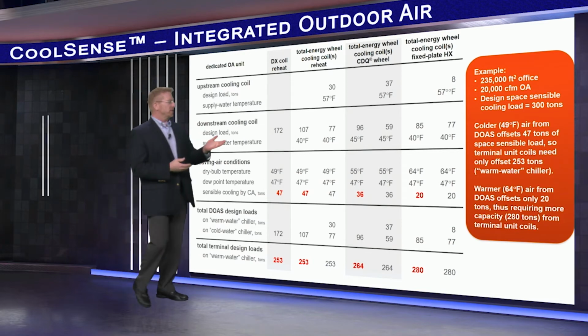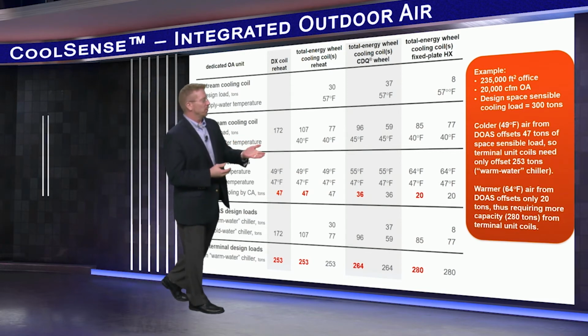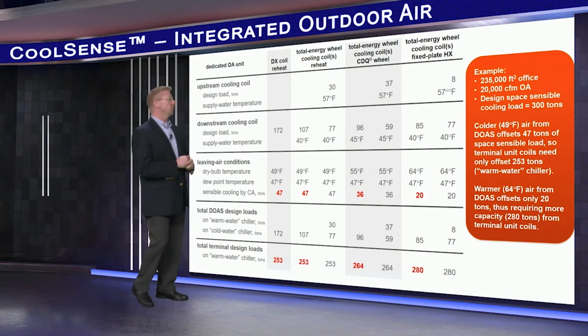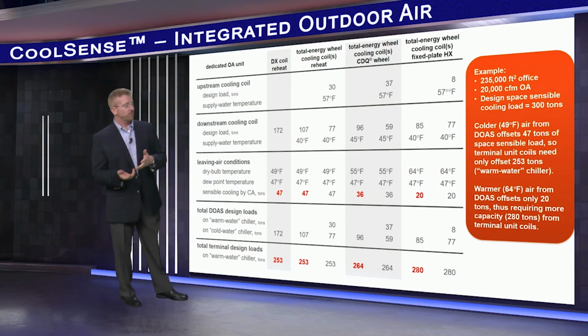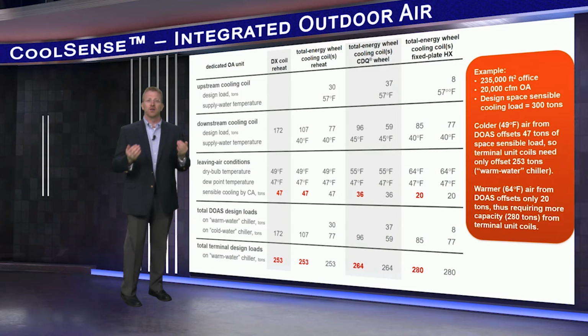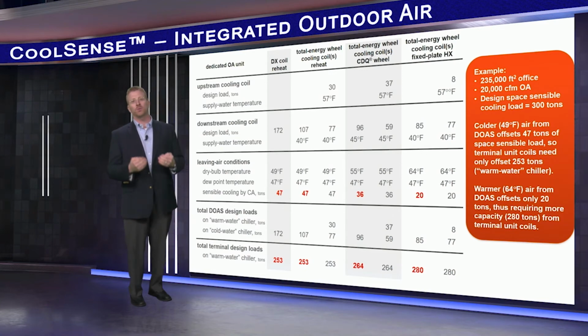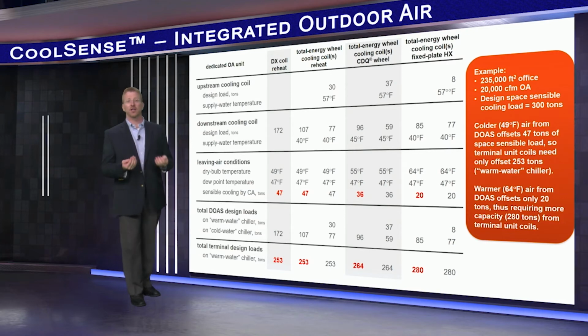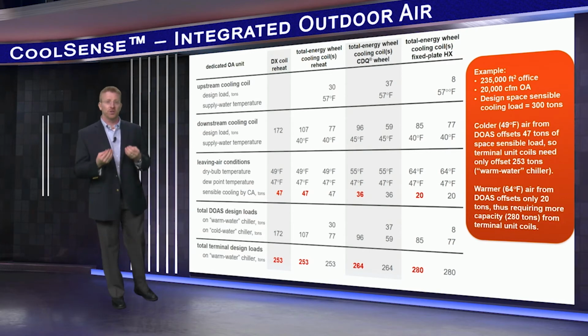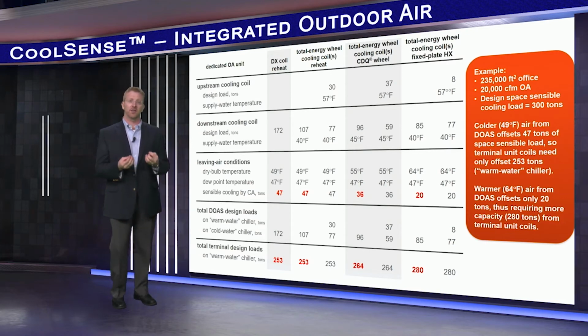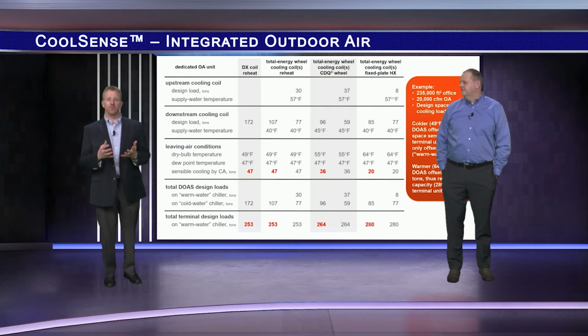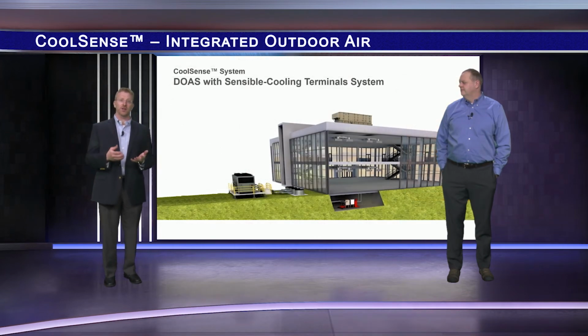As we move across the table, the loads shift between the warmer loops and the colder loops, shifting more load to the terminal boxes. The key takeaway? The CoolSense system has multiple degrees of freedom for the designer, enabling flexibility and customization of their designs using the basic building blocks that the industry is already comfortable with. So the load that we are shifting around means the chiller plants have substantial opportunities for customizing too.